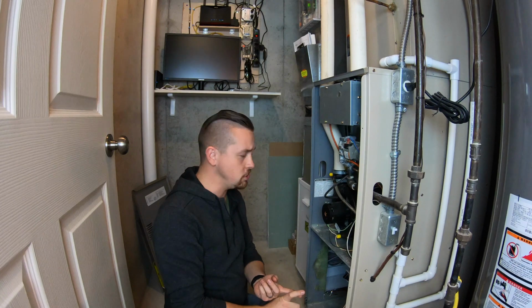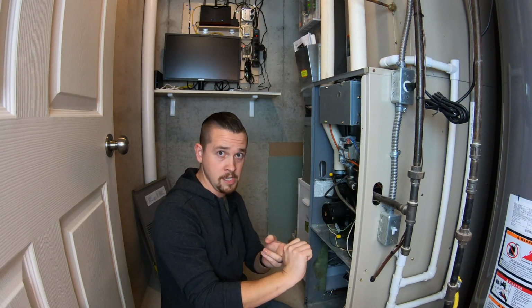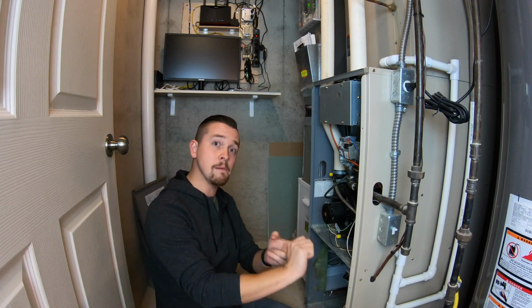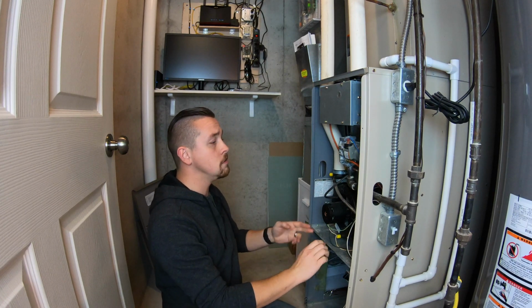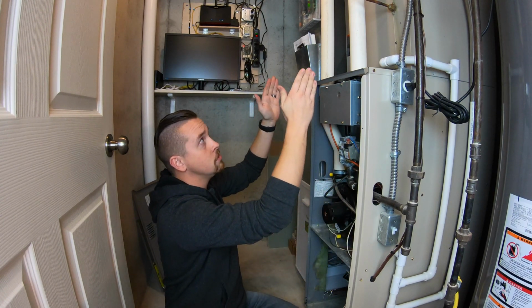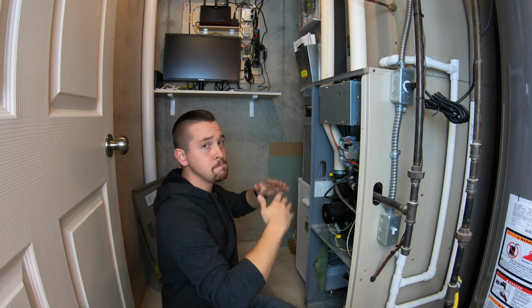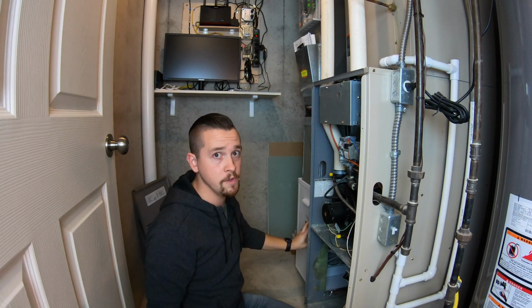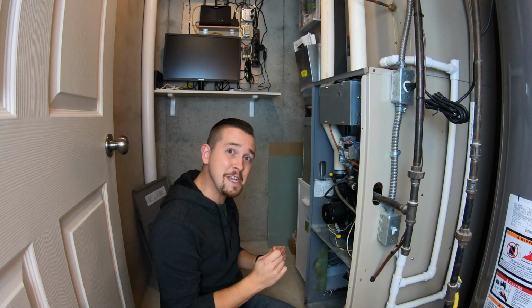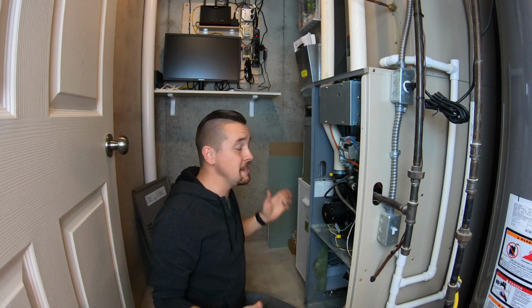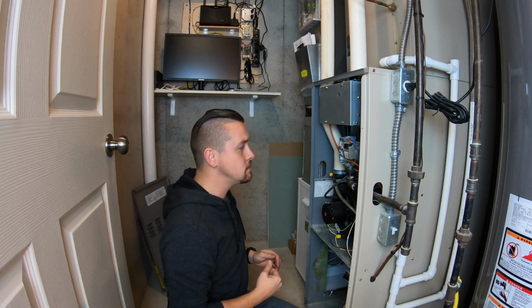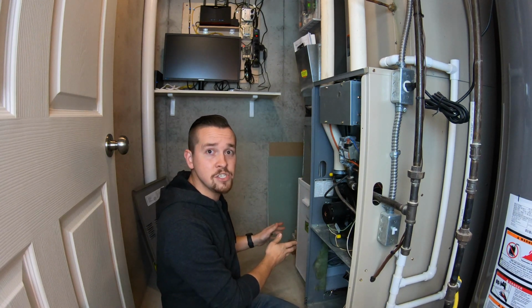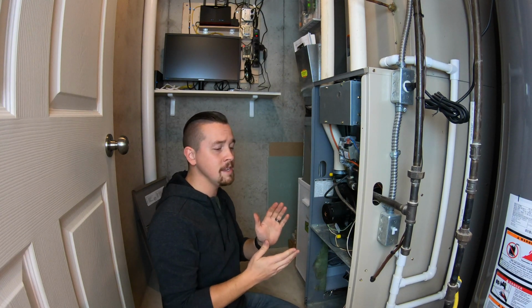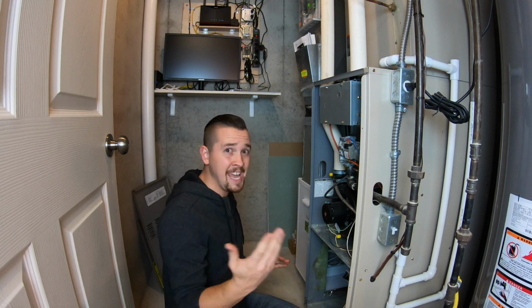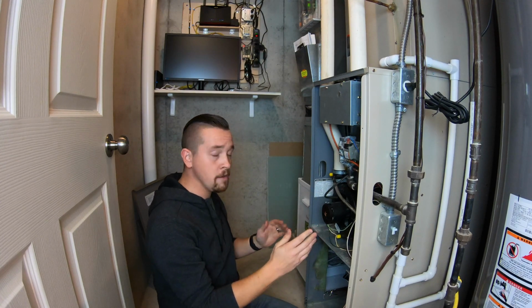Either your blower speed's too low, very uncommon if this is just a sudden issue. Your filter might be dirty. If you haven't changed your filter recently, you should probably pull that out and check it. Or maybe your secondary heat exchanger or your air conditioning coil is plugged up with dirt from running the system with no filter. Those ones are a little bit harder to fix on your own, but I have come across them in the last month here. I've come across both. So keep that in mind too. Filtration on the system is very important. I recommend getting at least a baseline filter that you can't see through to make sure you've got good airflow.